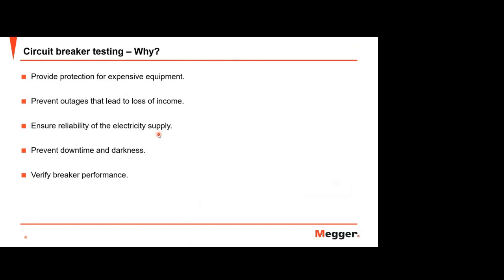So this is some of the reasons why we need to do circuit breaker testing. Of course, there are many reasons and more, but I just talk based on some of them. For example, the main reason is to provide protection for expensive equipment. So the main function of the breaker, as we know, is to protect your asset from expensive and high-cost failure. So we try to avoid that condition with circuit breaker testing, and also to prevent outages that lead to loss of income.